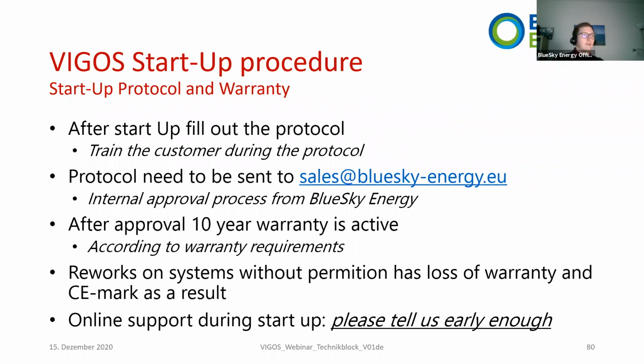Good. So after the startup, please also fill out the startup protocol and also train the customer during this protocol. The protocol also needs to be sent to BlueSky, sales at bluesky-energy.eu. And after an internal approval, we give you the warranty. Unfortunately, I'm not sure if it's also going to be 10 years for Vigos. So sorry if it is the same number. So reworks on a system without our permission has loss of warranty and CE mark as a result. So please be aware of that.